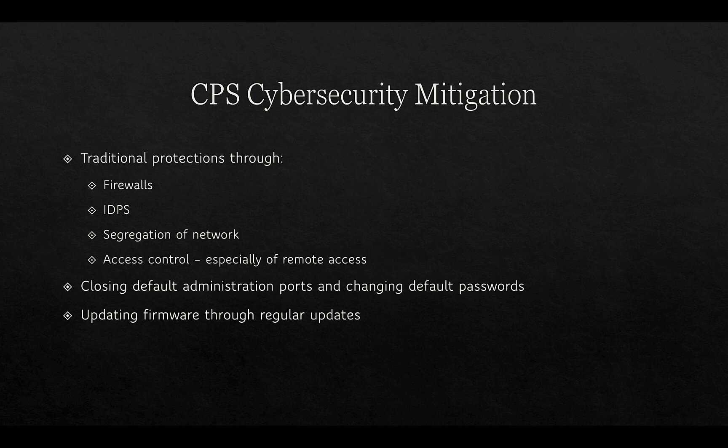In terms of mitigation, traditional protections through firewalls, intrusion detection and protection systems, network segregation, and access control — especially of remote access — is one approach. Closing default administration ports and changing default passwords is part of the hardening process, along with updating firmware through regular updates. If controllers don't need to be connected to the internet, keeping them disconnected is also an effective mitigation strategy.